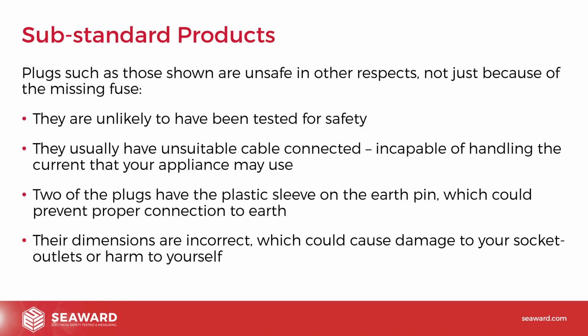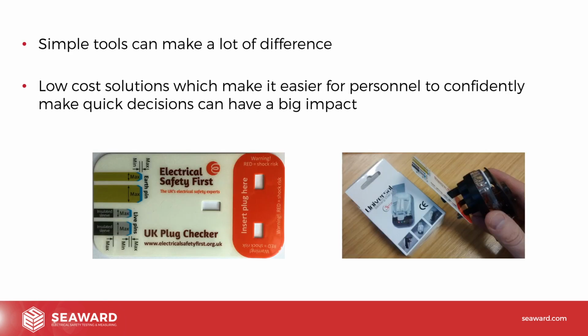Plugs such as those shown are unsafe in other respects, not just because they're missing a fuse. They're unlikely to have been tested for safety because they would have failed. They usually have unsuitable cable connected, incapable of handling the current that your appliance may use. I mentioned that before. Two of the plugs have a plastic sleeve on the earth pin, which could prevent proper connection to earth. And the dimensions are incorrect, which could cause damage to the socket outlets or harm to yourself.